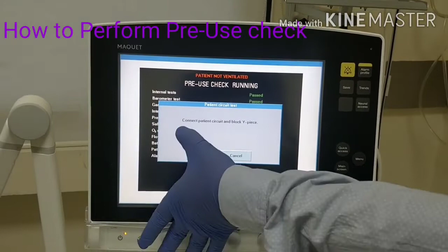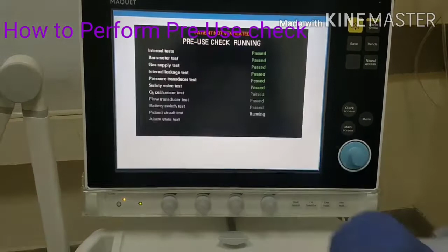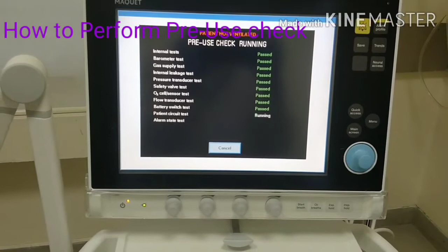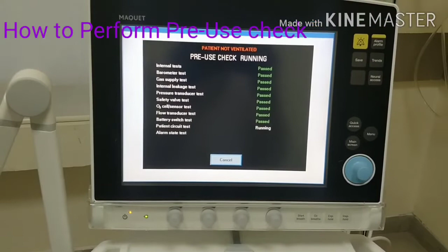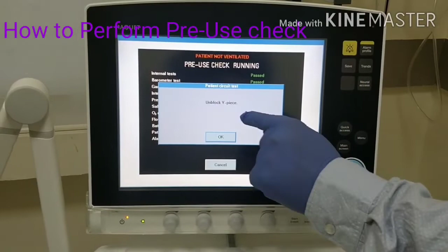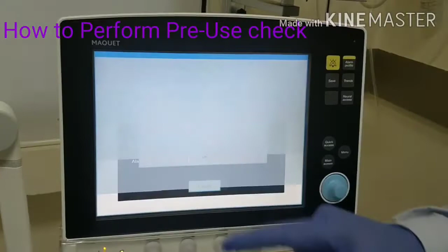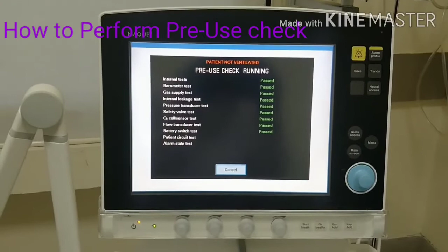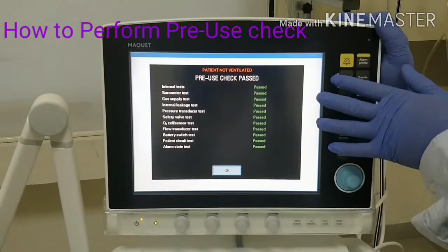Next, it will show you the patient circuit test. Connect patient circuit and block Y piece. Press OK. Next message: unblock Y piece, which means you have to remove one end of this pre-use check tube, and press OK. To complete all 11 tests, the ventilator requires a minimum of 3 minutes. So you have to wait for 3 minutes.